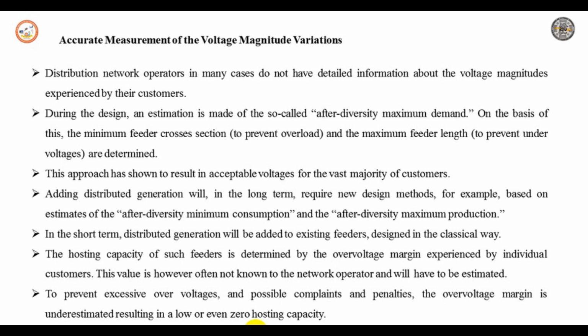The automatic metering equipment that has been introduced in many countries is often able to measure the voltage magnitude with a time resolution. Although not perfect, it will give sufficient information to provide an accurate estimate of this hosting capacity. By obtaining more accurate information on the actual voltage experienced by customers, network operators will be able to allow more distributed generation to be connected without the risk of unacceptable overvoltage for other customers. These measurements at the same time give the network operator information about the available undervoltage margin for future load growth. This is important information for planning future investment in the distribution network.